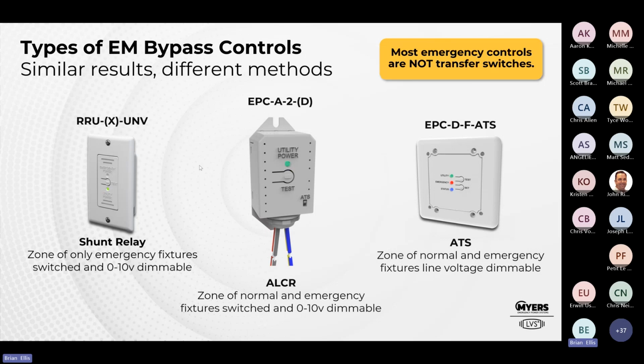Both the shunt relay and the ALCR relay are UL924 listed bypass devices. The reason they're bypass devices is that they never allow you to power the emergency fixture from utility. You're only powering emergency fixtures from emergency power. If you want to power from utility or emergency power, then you have to use an automatic transfer switch, which has to be listed UL1008. If you transfer from one source to another, the device that you use must be listed as UL1008.